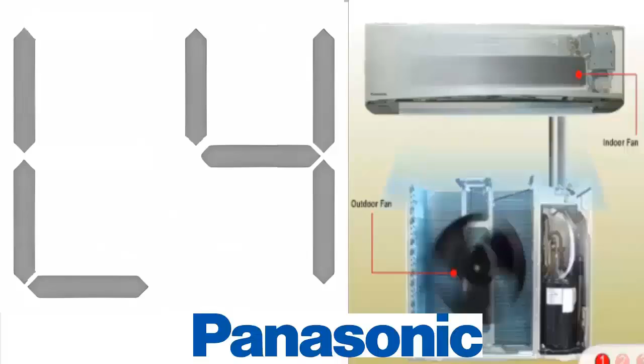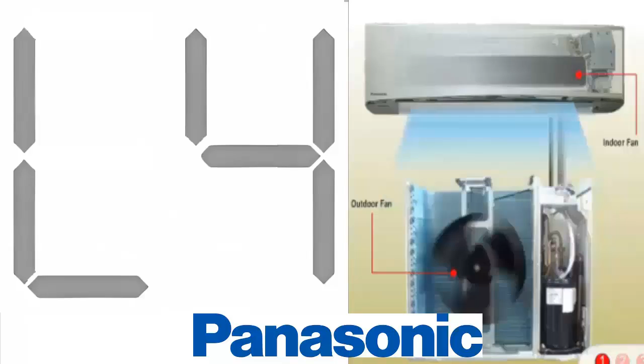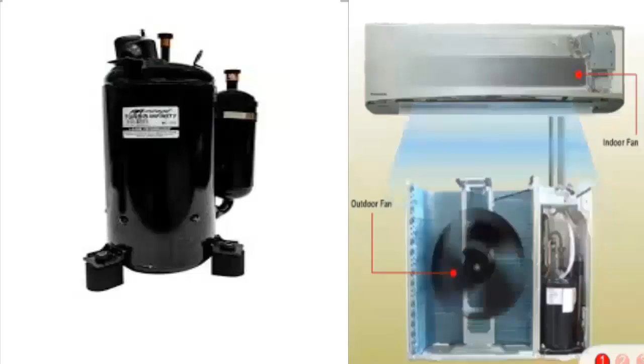Generally, the error code L4 in air conditioning units is directly associated with the following causes. 1. Problems with the compressor that prevent it from starting normally. 2. Compressor startup with irregular current consumption in one of the motor's coils, or overall current consumption above normal.